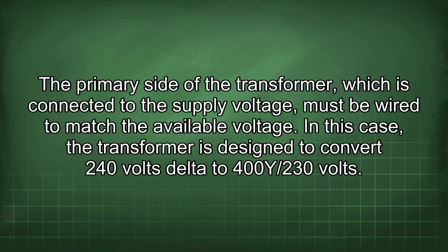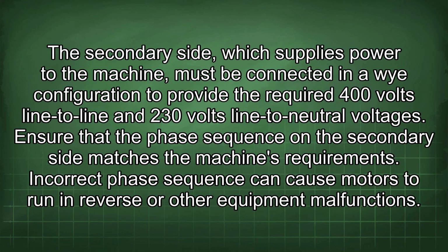The primary side of the transformer, which is connected to the supply voltage, must be wired to match the available voltage. In this case, the transformer is designed to convert 240V delta to 400Y/230V. The secondary side, which supplies power to the machine, must be connected in a Y configuration to provide the required 400V line-to-line and 230V line-to-neutral voltages. Ensure that the phase sequence on the secondary side matches the machine's requirements. Incorrect phase sequence can cause motors to run in reverse or other equipment malfunctions.